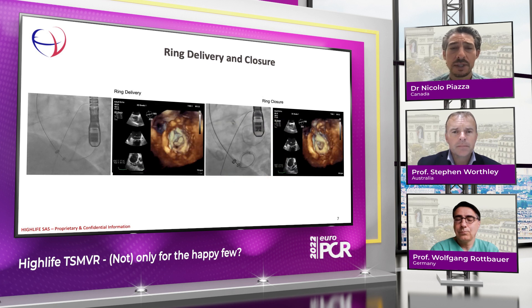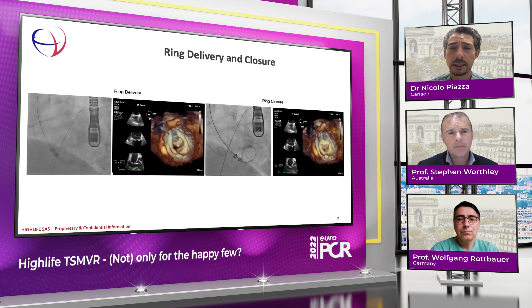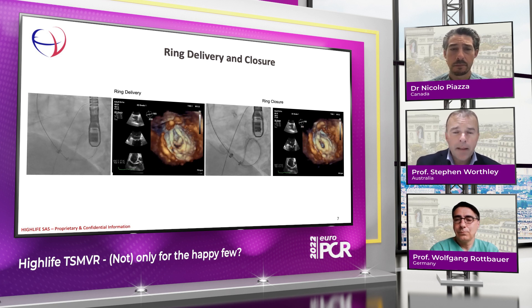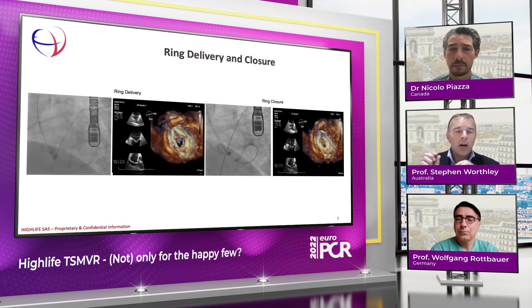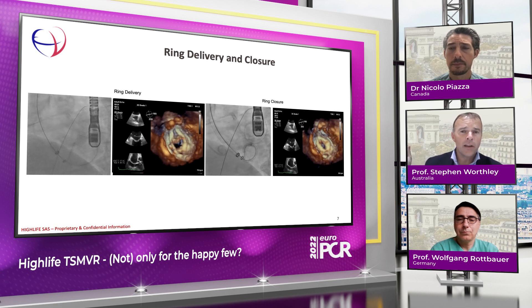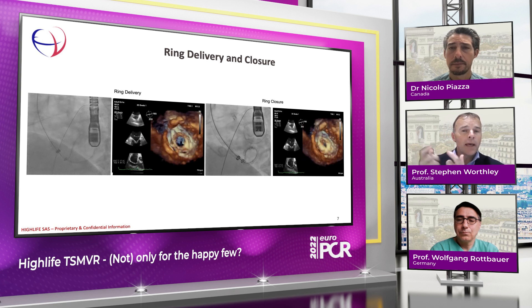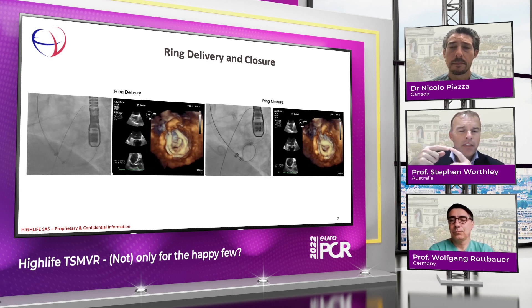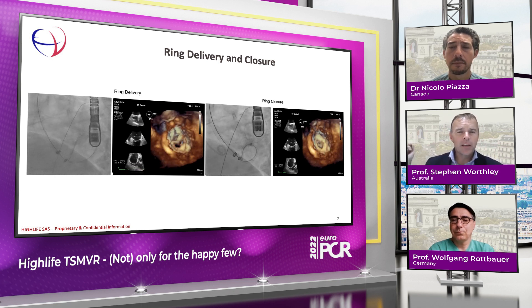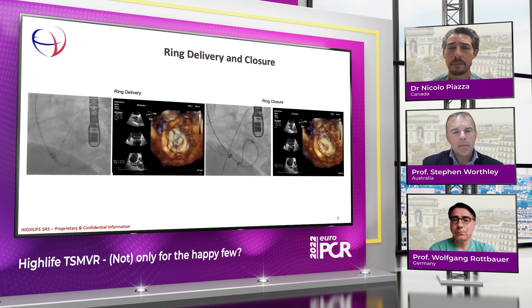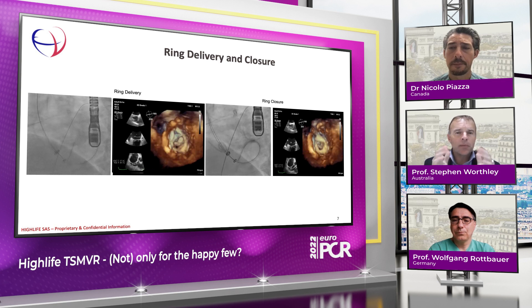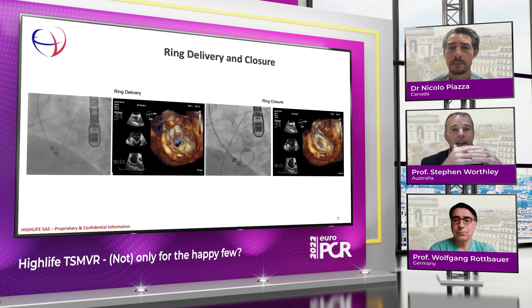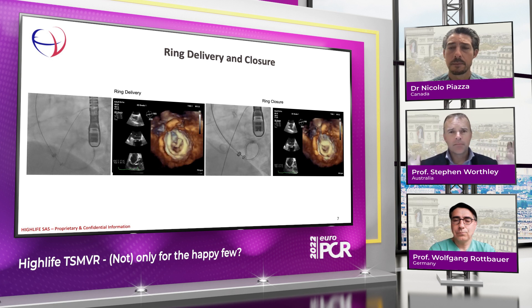Steve explains ring deployment: now that you've got the loop around, the sub-annular implant ring is quite simple — it's an elegant design. On the two exteriorised ends of the 300-centimetre Terumo glide wire, you place the two ends of what will become the ring. It's like a long tube whose ends will intussuscept into each other with a one-way valve structure so they cannot come back out. You drag the ends of the ring into each other, they intussuscept, a locking mechanism holds them, and the ring is deployed.